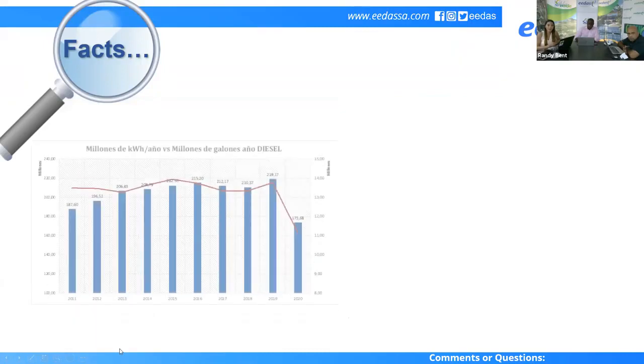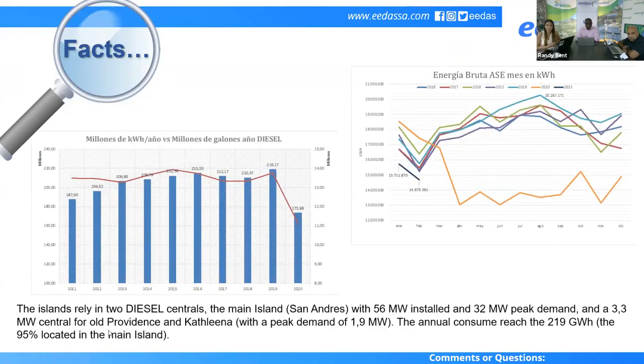The islands rely on two diesel centrals. The first and bigger one is located in San Andres with an installed capacity of 56 megawatts and 32 megawatts peak demand. In Providence, the other central serves Providence and Catalina with 3.3 megawatts installed capacity and 1.9 megawatts peak demand. Annual consumption across the islands reaches up to 219 gigawatt hours, where 95% is from San Andres.